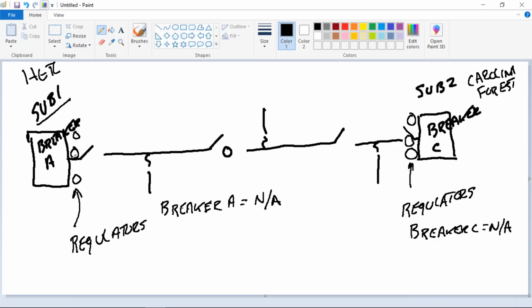And actually, there have been some cases where the breaker has gone into alarm and you're backfeeding into the transmission circuit. Because from here, we go to bus, we go to low side switch, we go to transformer, and you're actually going to start trying to backfeed the transmission line through a substation breaker. Now there are preventative measures in here. Inside a breaker, they've got a setting for reverse power flow. Once it recognizes that, it's going to lock out both breakers, so you're not getting into that situation. But it is essential that the regulators and the voltages are matched between the two substations.